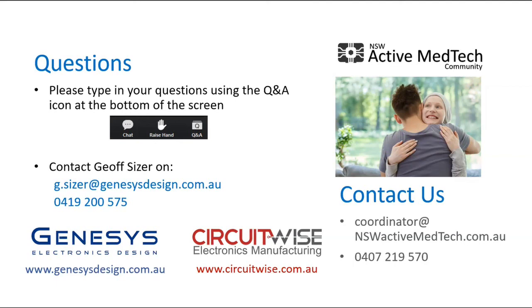They're absolutely enmeshed in the quality system, because quality system requirements are defined by ISO 13485, which you'll have heard mentioned a few times today. And the clauses that I've referenced are the design control process from section 7 of ISO 13485. So they are inextricably enmeshed. So your design and development procedures under your quality system will define the requirements for design control.